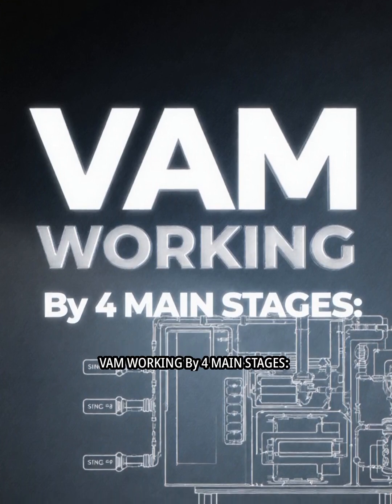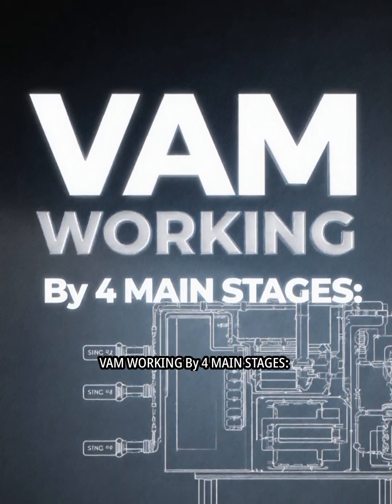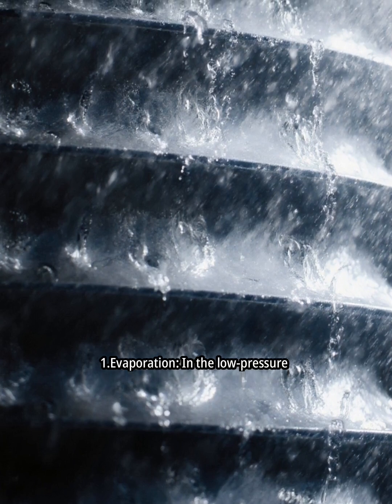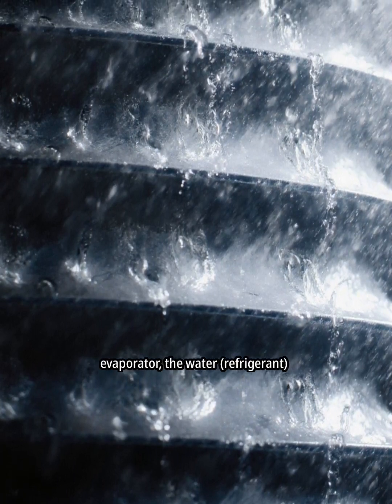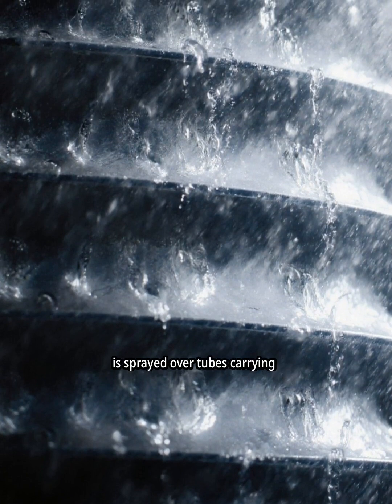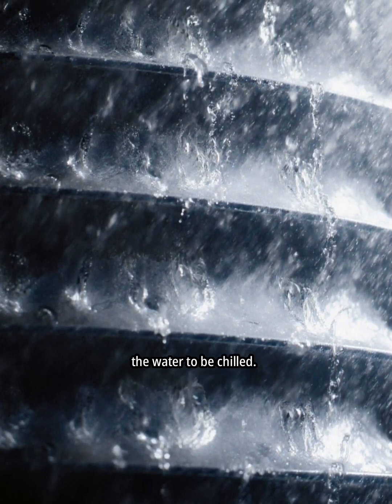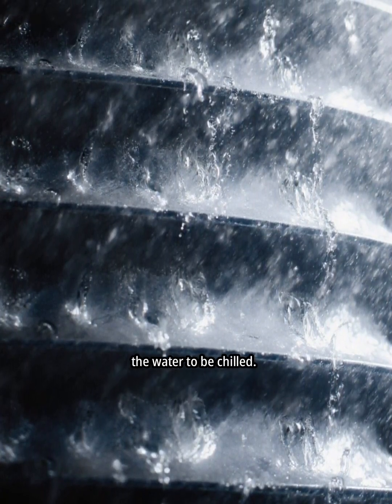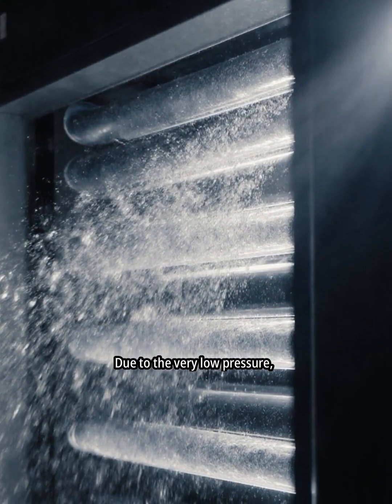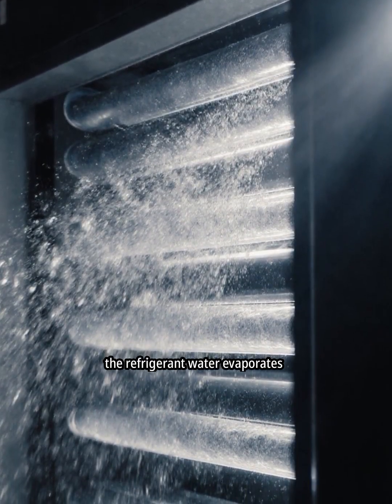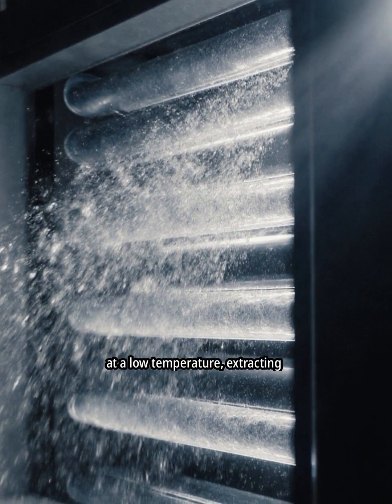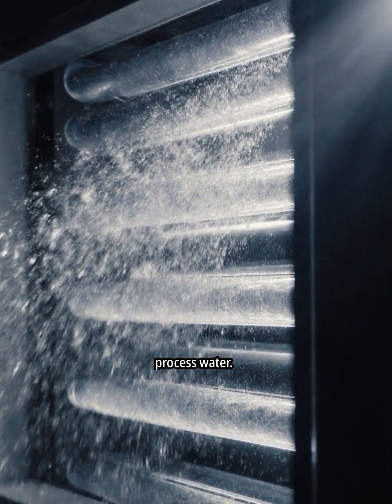VAM works in 4 main stages. 1. Evaporation. In the low-pressure evaporator, the water, refrigerant, is sprayed over tubes carrying the water to be chilled.